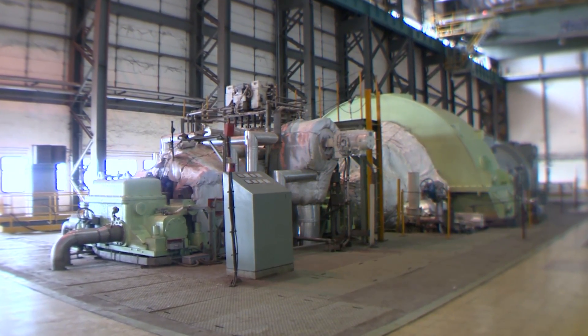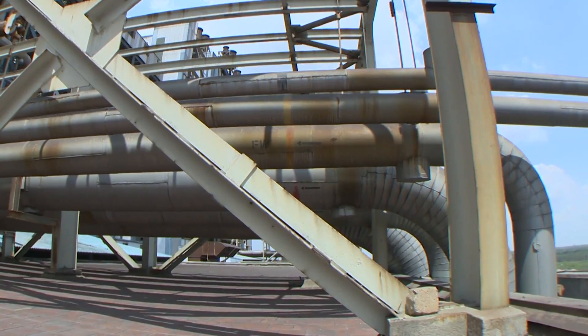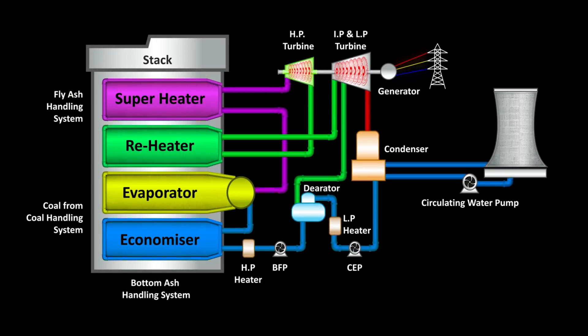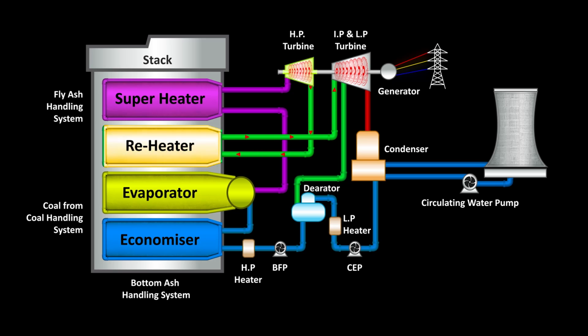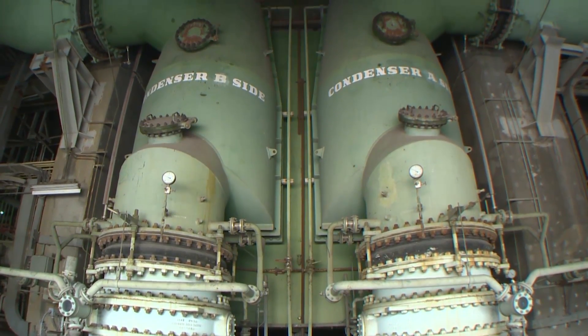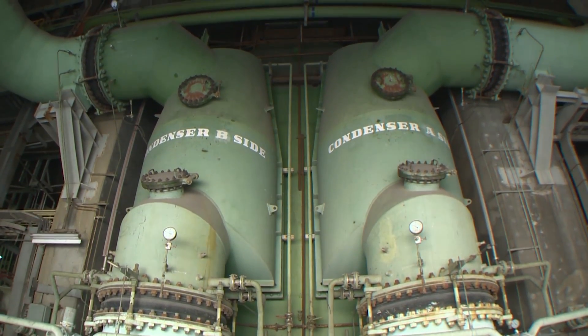Boiler supplies superheated steam to HP turbine through main steam lines. After the work is done, the exhaust from HP turbine reaches the reheater arranged in the boiler through cold reheat lines. The reheated steam is taken to IP turbine through the hot reheat line. Then the steam expands in IP and LP turbines.